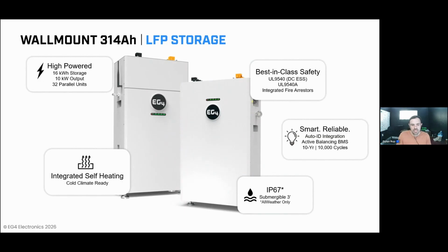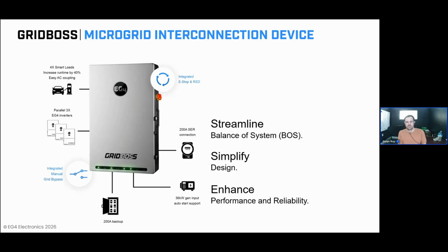it could even start. And then finally, pulling the FlexBOSS lineup together is the EG4 GridBOSS, our smart interconnection device. The core function of the GridBOSS is really to enable a 200 amp interconnection for the energy storage system, giving you full home backup for a 200 amp service and the ability to safely island behind the meter and continue to power the loads in the home, regardless of what might be happening on the utility side of the meter. However, despite that capability, or in addition to that capability, I should say, the GridBOSS really delivers a ton of additional features and benefits to make the FlexBOSS lineup even more powerful and reliable.